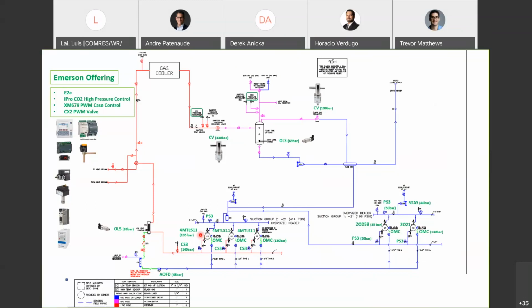You start at your medium temp compressors. Well, we have medium temp compressors, 4 MTLs. Look, those 4 MTL compressors need a mechanical pressure switch. We have that. It's called the CS3. And it's a lot better than the bimetal ones that they were using before. This one is not temperature affected. Some of those cheap bimetal ones that were used in the past, as the discharge temperature started to heat, their set point would change. That was very frustrating for OEMs. So a CS3, I'll show you what that looks like.